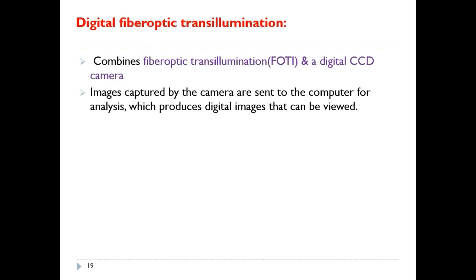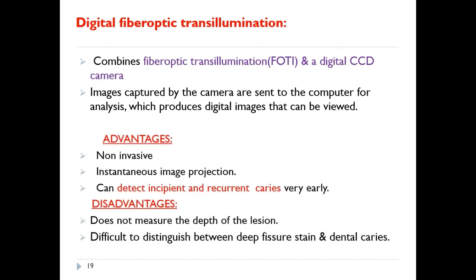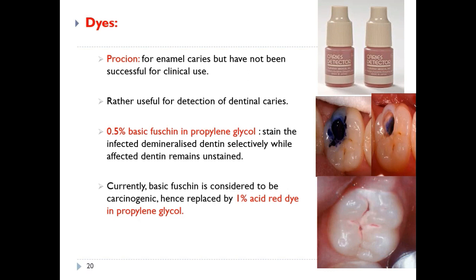Digital FOTI combines fiber optic transillumination with a digital CCD camera; images captured are sent to a computer for analysis and can be viewed digitally. Advantages include being non-invasive, providing instantaneous image projection without need for film development, and detecting incipient and recurrent caries very early. Disadvantage: it does not measure the depth of the lesion and it is difficult to distinguish between deep fissure stain and dental caries.